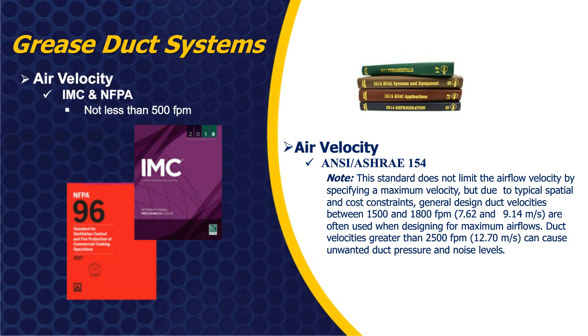Now, ASHRAE still makes a note in their standard that they don't limit the airflow by velocity by having a max. They do still adhere to the 500 minimum, but it says it's common to size these systems at 1,500 to 1,800 feet per minute. If I'm sizing grease duct systems and I'm going to utilize 500 feet per minute, the grease duct systems are going to become massive to reach those low velocities. So it's still not uncommon to size at 1,500 to 1,800. One note you'll see in the ASHRAE standard is that velocities greater than 2,500 start having risk of potential noise levels and so forth, what you might call a tin-canning effect in the ductwork as air goes through at those high velocities.